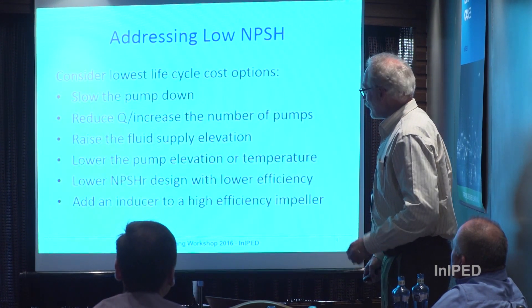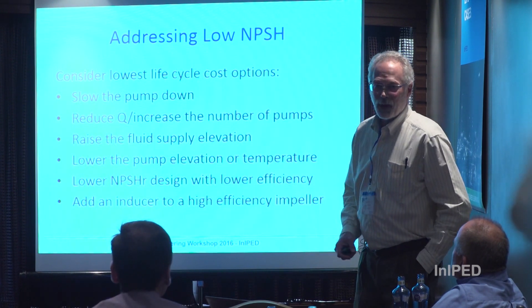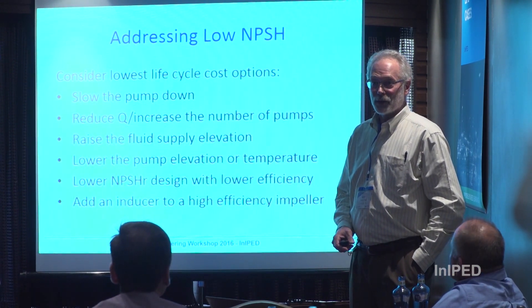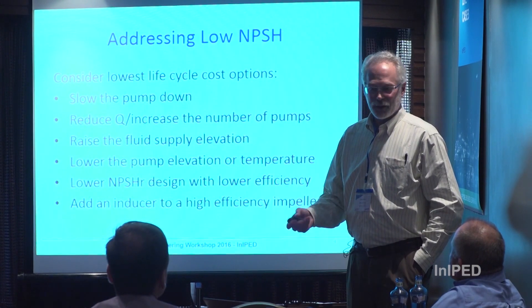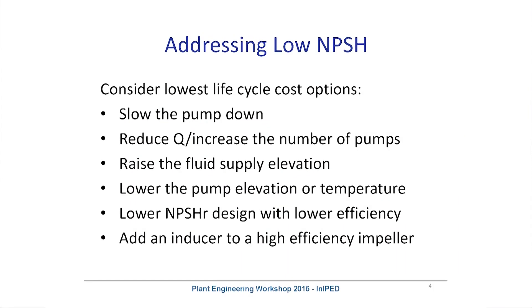Before we get into inducers, let's talk about what you can do instead. You can slow the pump down — the slower the pump, the less challenging any NPSH performance requirement is. The same applies to flow: if you reduce the flow, it's less challenging for any one pump. You could also raise the fluid supply — put your tank up on a stand — or lower the pump.